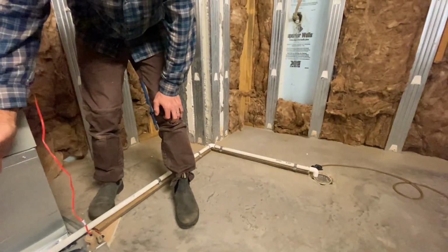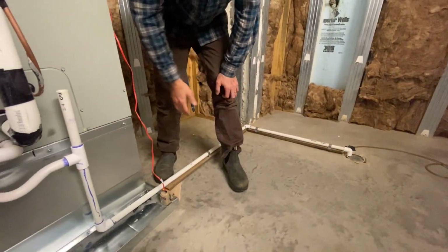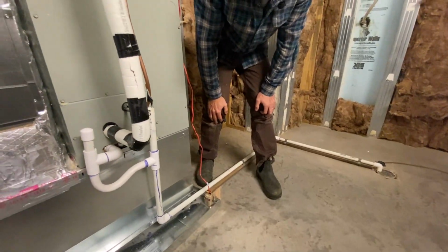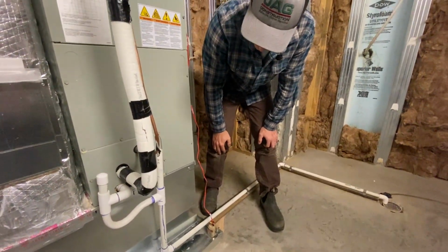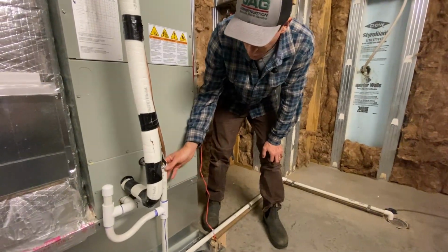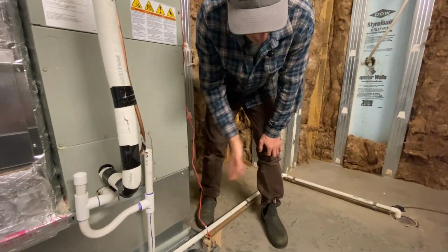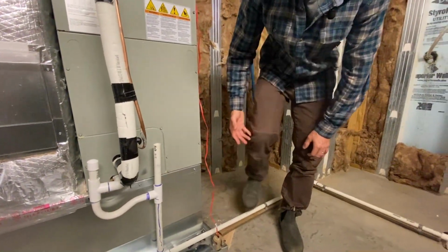You want to make sure that this line is always connected to that drain. You want to make sure that it's not broken. You want to make sure that it stays intact and it's doing its job, because if at some point this condensate line breaks, you would then have a water leak in the home.